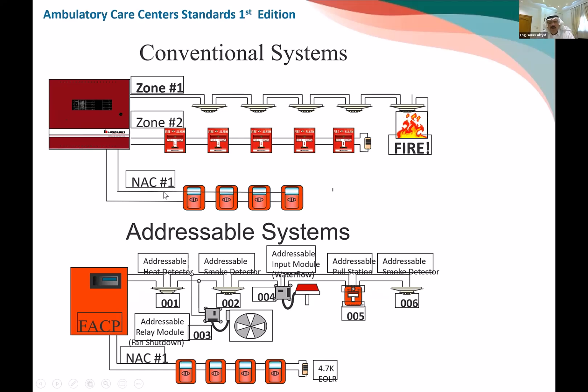Now, when we visit your hospital or center, we need to check that the fire system is working. We check the fire alarm. There are no defects, no faults, no alarms, and the system is in a ready condition. With the addressable one, you can know the room itself.